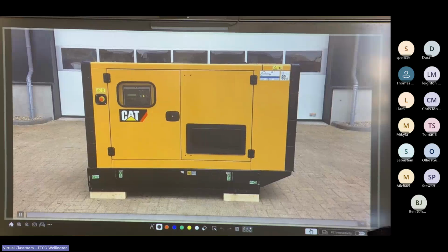Gensets normally have a system on them for letting you know how many hours it's run for, because it doesn't matter how old the genset is, it just matters how long it's been run for. The genset could be 5 years old or 10 years old, but the 10-year-old one may not have been used as much, so it's only got a couple hundred hours on it, whereas the 5-year-old one could have had 500-600 hours on it because it's been used continuously.